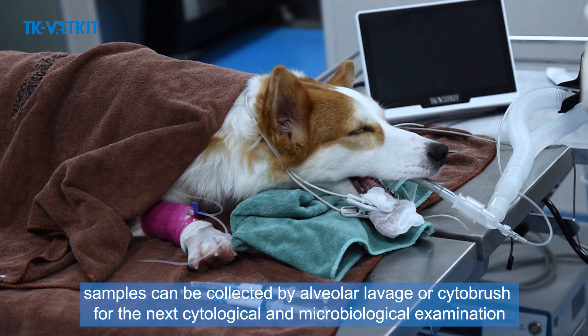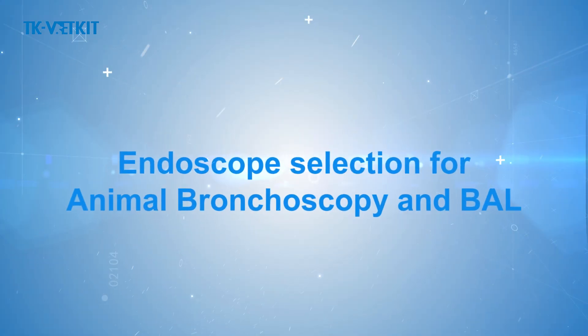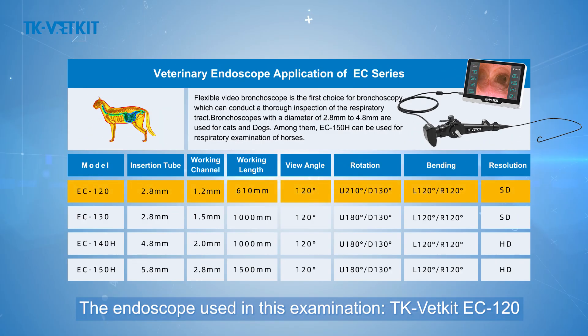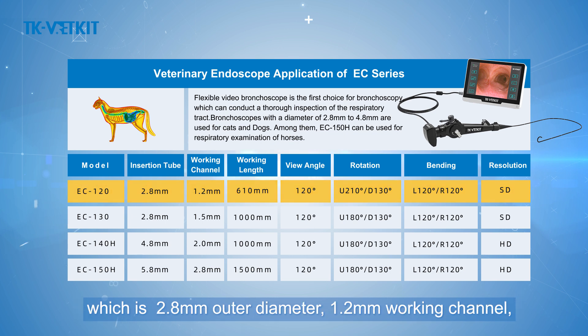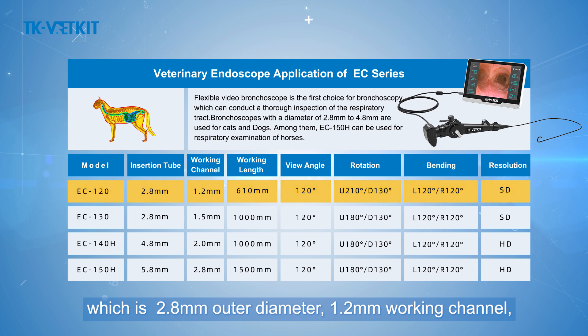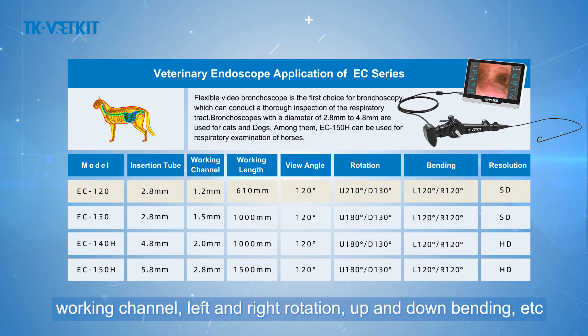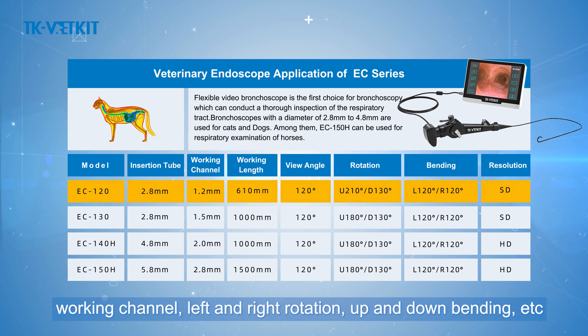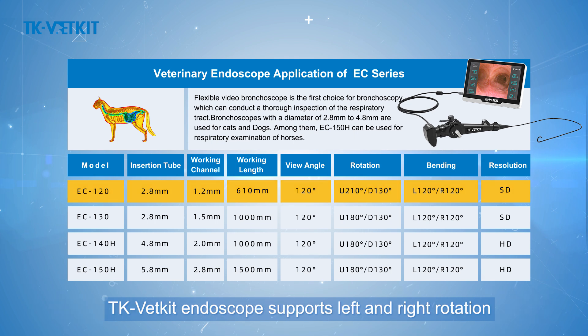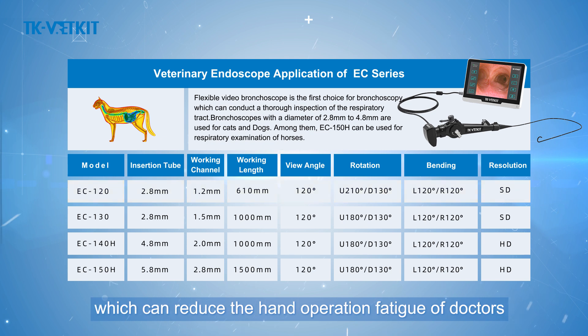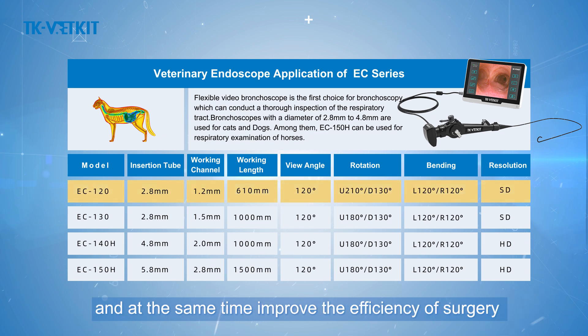Scope selection for animal bronchoscopy: the endoscope used is the TK-Vetkit EC-120, which has a 2.8 mm outer diameter, 1.2 mm working channel, and 610 mm working length. It features a suction channel, working channel, left and right rotation, and up and down bending. The left and right rotation function reduces hand fatigue and improves surgical efficiency and success rate.